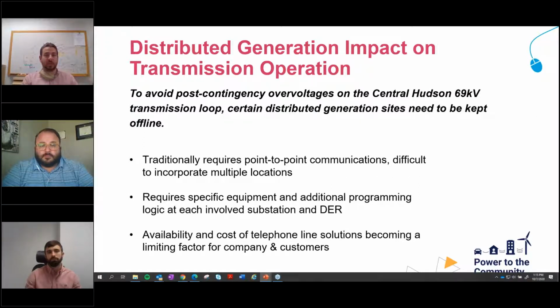The old school, traditional way was a hardwired DTT solution — you get a copper line from the phone company running from substation to site, and use direct transfer tripping schemes, linking the circuit breaker at the substation to the customer site breaker, sending signals to automatically trip it off. That's easy for a simple situation. But here with this loop, you've got multiple sites, multiple breakers, multiple configurations. It would be very complicated to program a conventional system to handle all the possible configurations of this loop, and to add additional sites. Very complicated, and very costly.